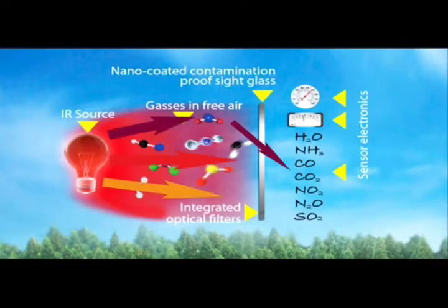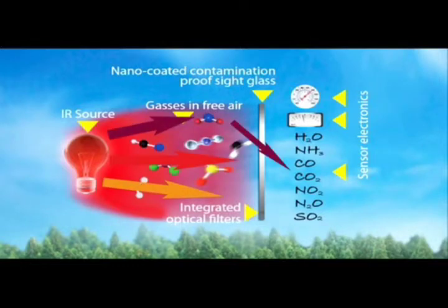We emit a broadband infrared radiation and CO2, for instance, will absorb this radiation at a specific frequency. So if we let exactly this frequency pass through our sight glass, we can measure with the electronics on one side of the glass how much CO2 is on the other side.